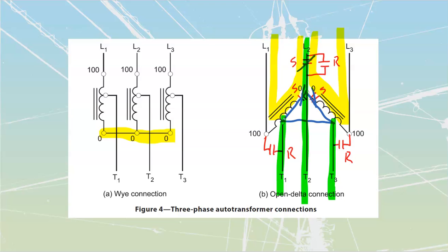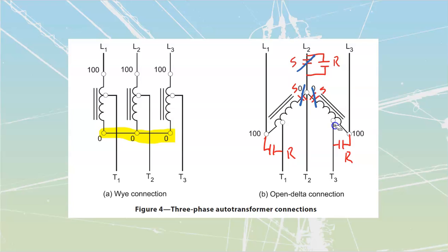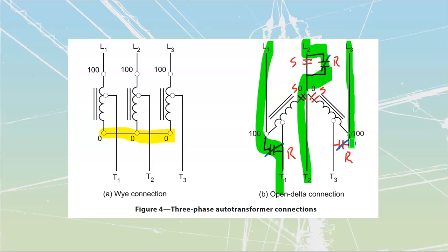That's during start. Then our contacts are going to close, just like we saw in the other one there. And when they close, my contacts are going to change state. When they change state, all of my S's open up like this. So now I'm going to be open out to all of my loads over here. I'm not going to have any complete connection. And then I'm going to close in on these ones over here on my R's. And that's going to allow me to now pass current directly through. Oops, sorry, that one's going to go through. Directly through and down to my motor itself.